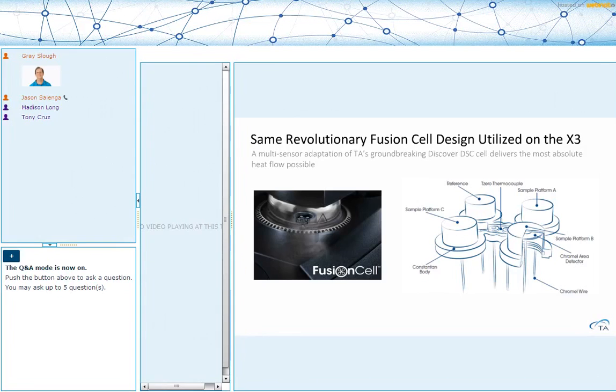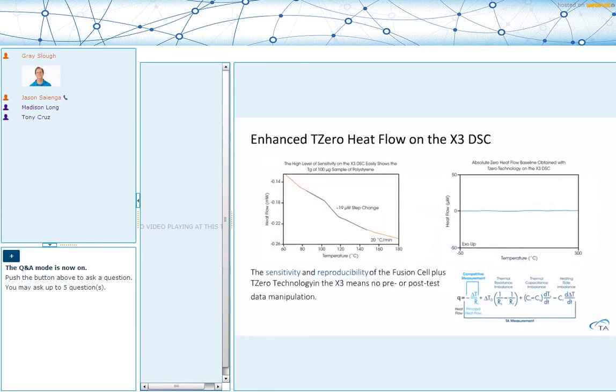cell, thus providing us an independent temperature measurement, and really it provides us a much higher degree of results, heat flow results, temperature, enthalpy accuracy. But it's not just the hardware. Obviously, we are incorporating an adaptation or a similar Tzero heat flow equation to this particular design. But as we've discussed with the previous Discovery DSC, as well as some prior Q-series DSCs, the TZero heat flow equation is significantly more detailed than a traditional heat flow measurement.